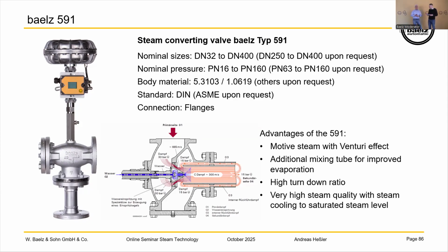Depends on what kind of cooling system you use. For motive steam systems, there is not even, you can say, half a distance of the steam pipe. That's what I've heard a lot of times. This is not correct. You have to check how much water you put in and what system you are using. I would say minimum, in normal case for our valve, around 3 meters. For normal injection with normal nozzles, not motive steam, I would say minimum 7 to 10 meters. But it could also be up to, depending on when it's a lot of water.